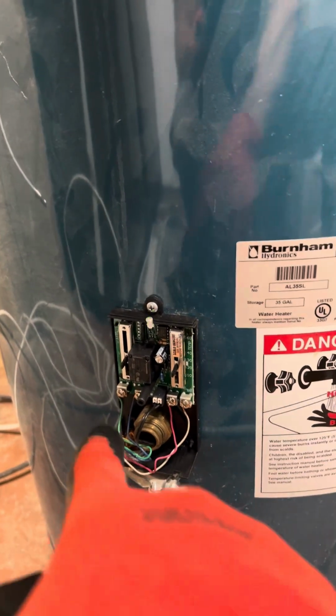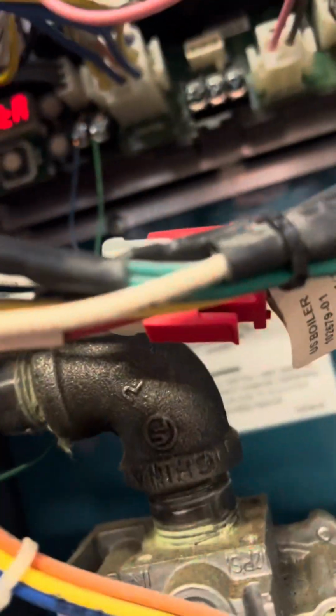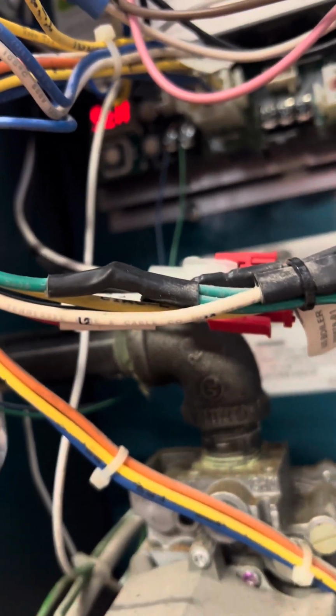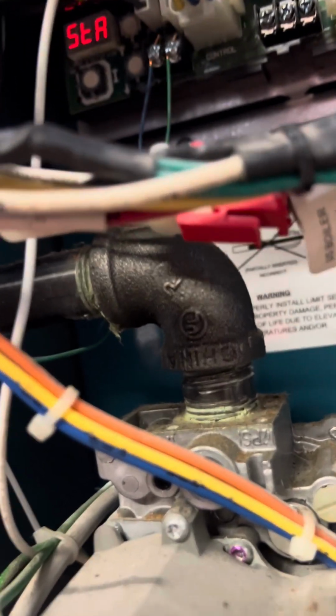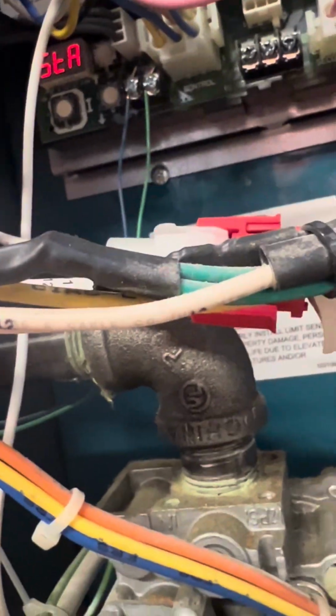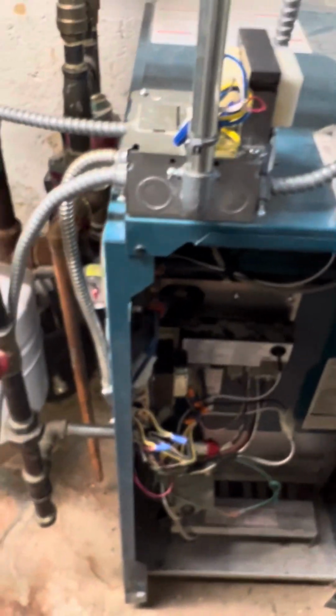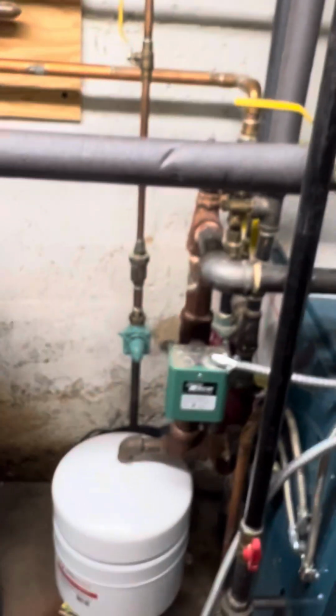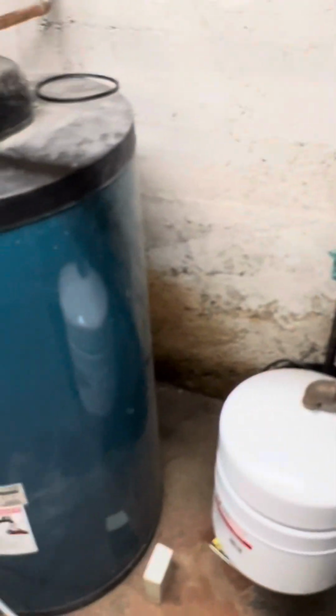And like I said, that blue-green goes through here into this box, down through here, and it comes out right there. See that? Right there, that blue-green. And that will tell the boiler to turn on, and that will actually supersede all the zones as well. But that's the priority. The hot water is always priority.